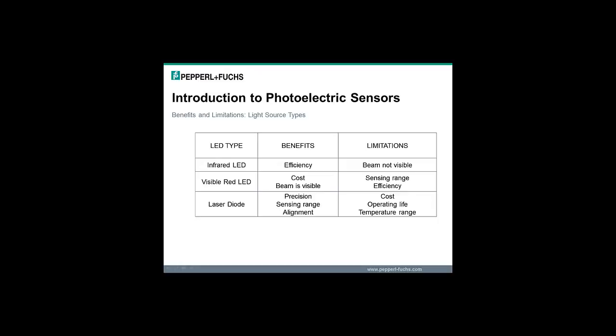For each benefit a light source may have, there is at least one limitation. Infrared LEDs are very efficient, meaning more light is reflected from the object of interest rather than absorbed. This makes them particularly suitable for applications where the object of interest can vary in color and the distance required for detection. The most significant limitation with infrared LEDs is that the emitted light cannot be seen by the human eye, making alignment extremely difficult.